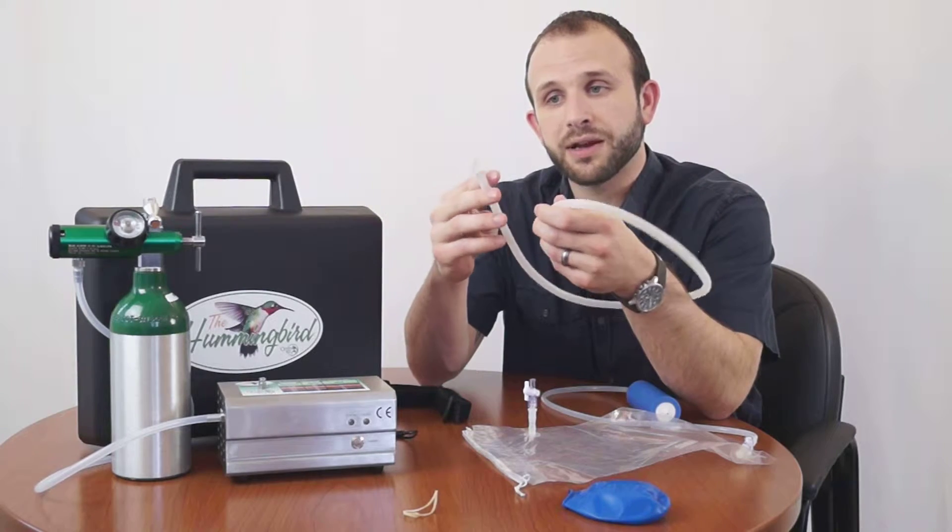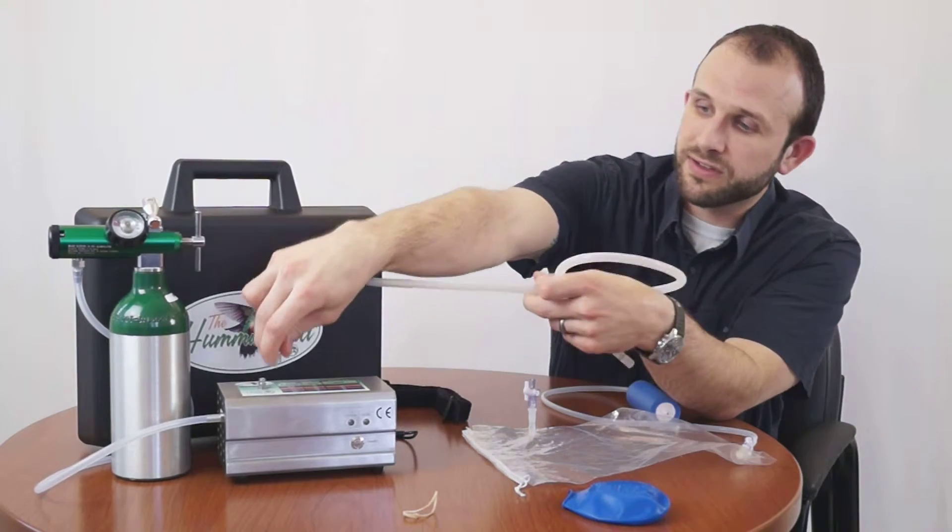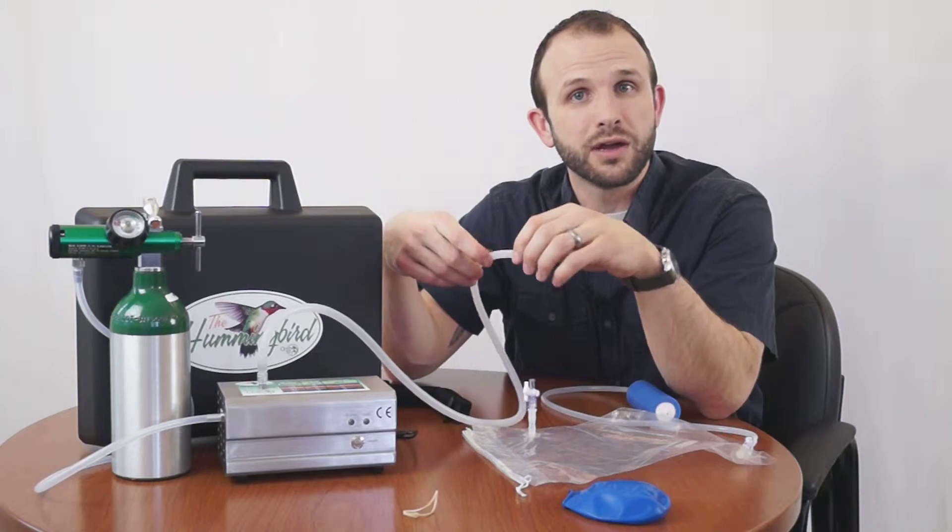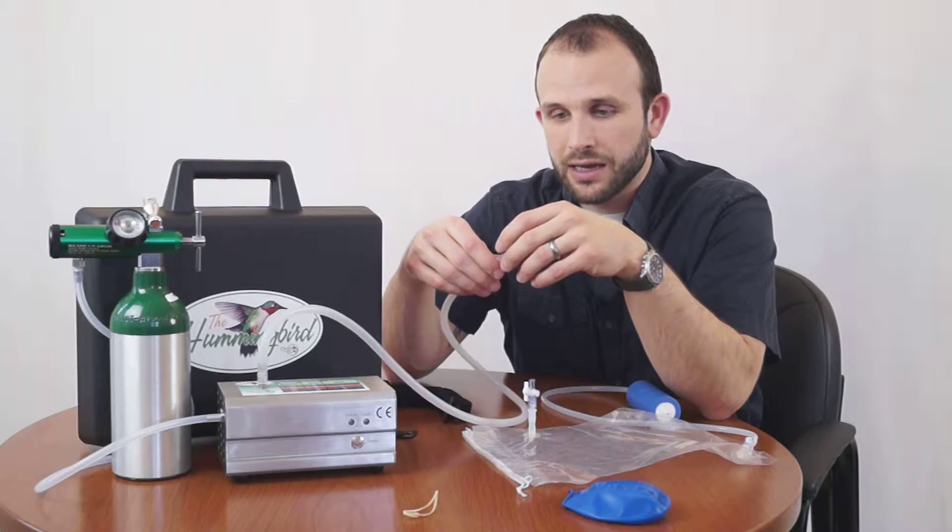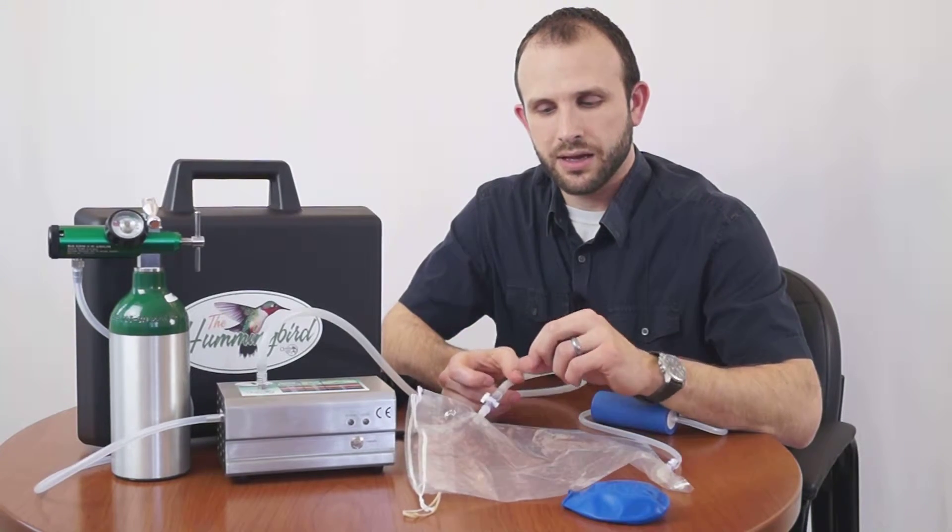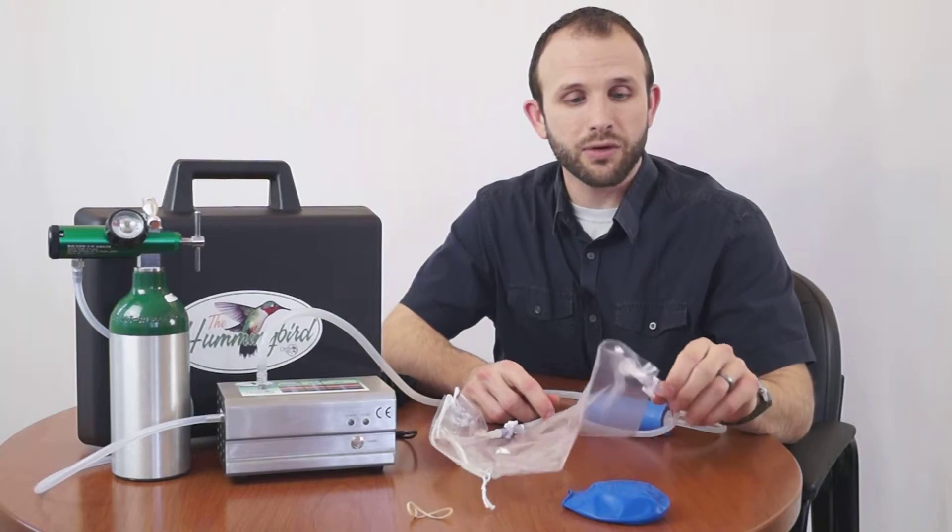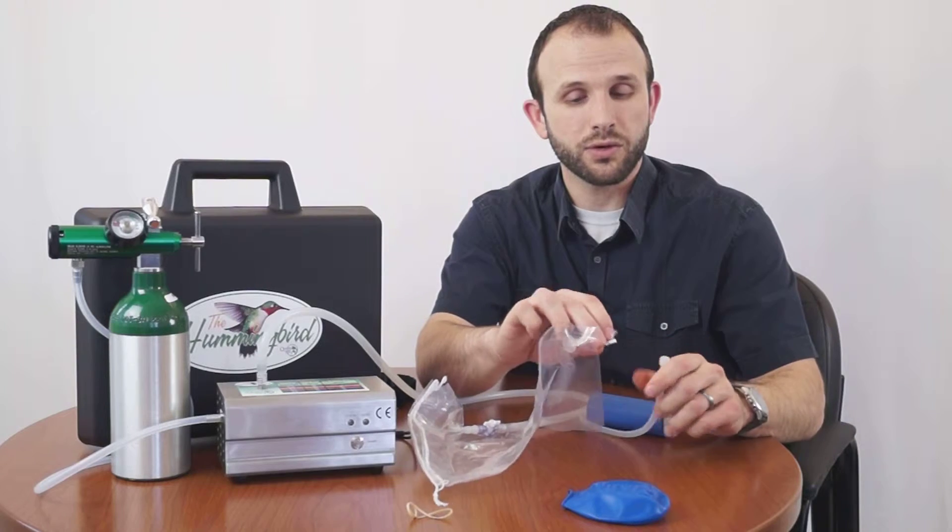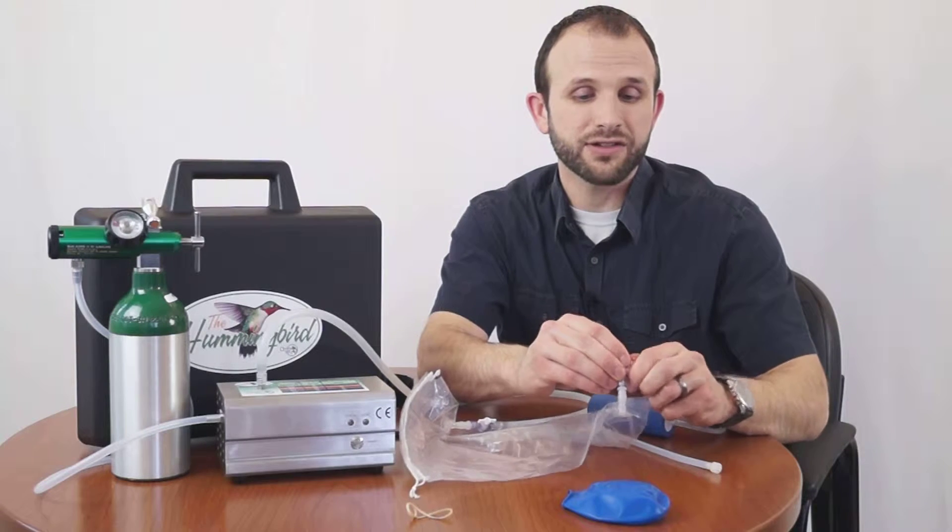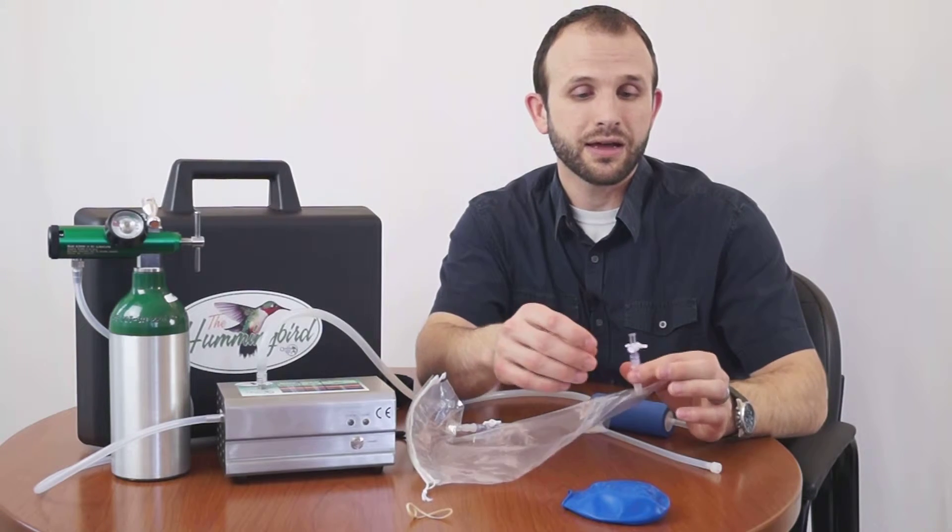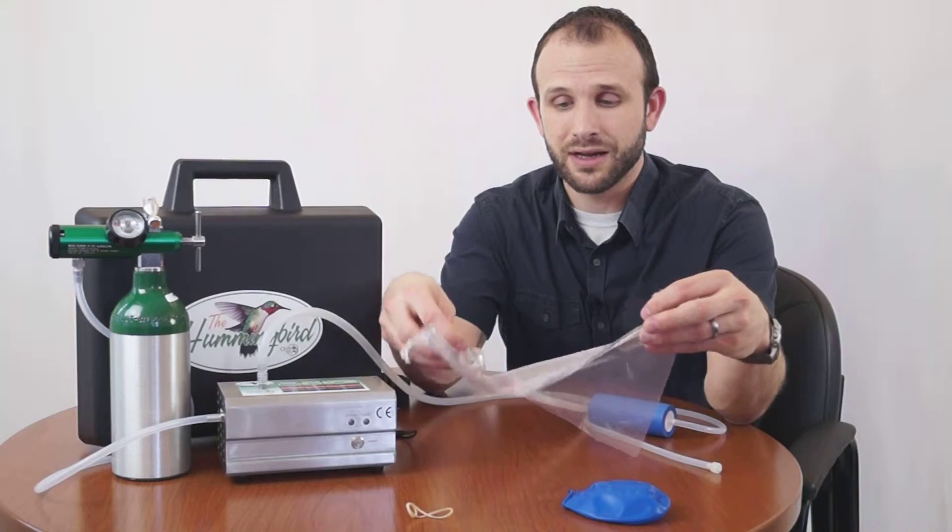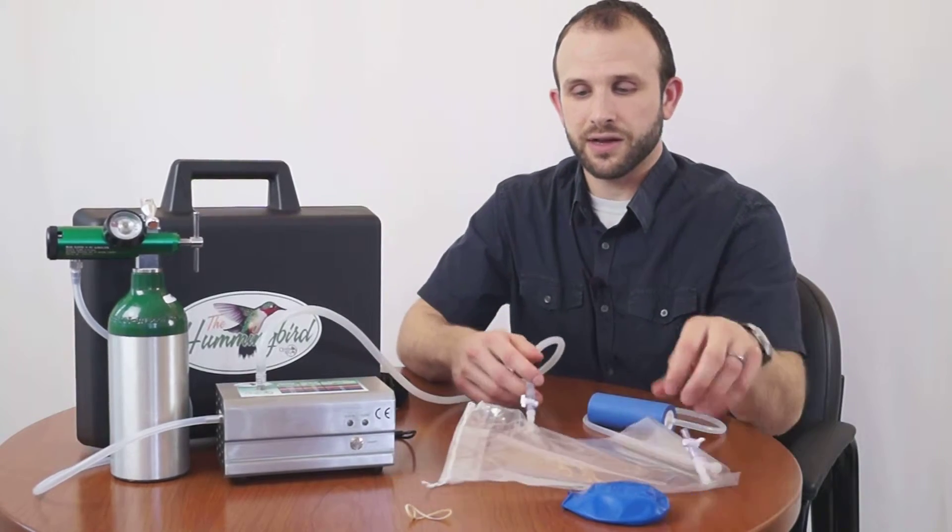What I'm going to do here is take my silicone ozone-resistant tubing and connect that directly to my Hummingbird. Now I would have had my Hummingbird, if I'm going to be treating, warming up for a minute or two before I start using it. Then I'm going to take the other end and connect it right here to the bag. I will mention that we don't actually have to connect the destruct until we're ready to end the treatment. We're going to just make sure that if we don't have our destruct connected, we're going to turn that valve off and make sure that ozone isn't flowing out as we're treating.